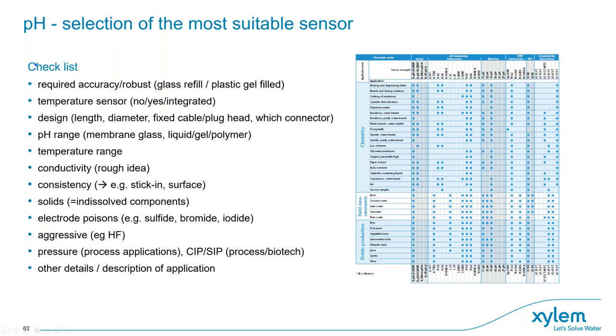When selecting an electrode, consider: the main requirement for accuracy — glass refillable or robust plastic; whether an integrated temperature sensor is needed; the connector and cable type. If you need to measure from pH 0 to pH 14 with the best possible accuracy, you need at least two electrodes — one standard type and one for the high alkaline range. If you are not happy with your current electrode, it is better to describe your application completely so the right recommendation can be made, rather than just asking for a similar replacement which may have the same limitations.